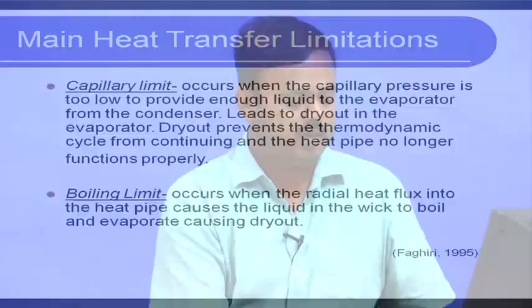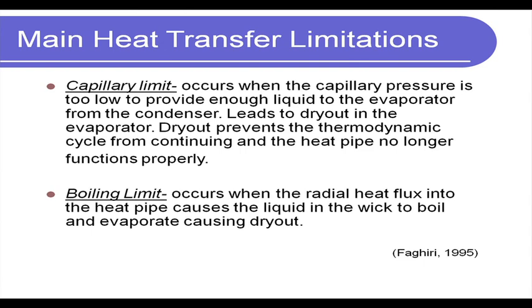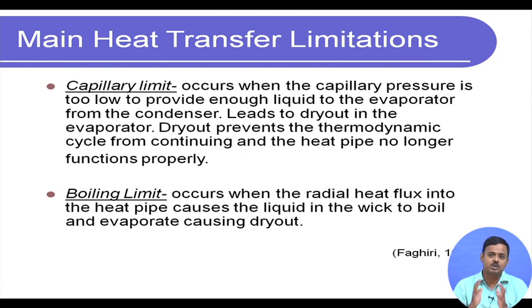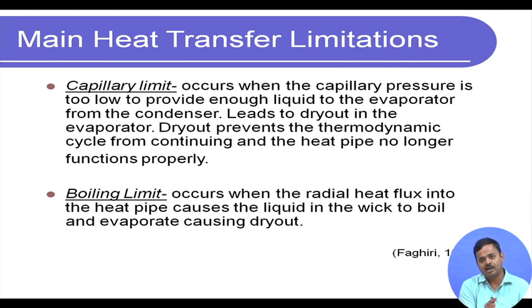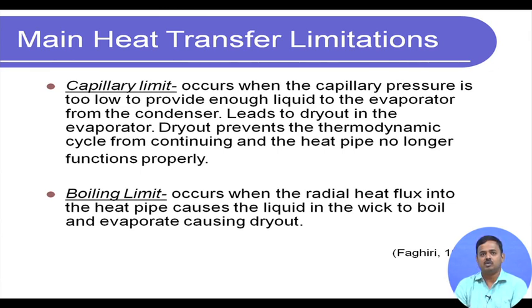Now let us go over the operating limits of a heat pipe. The first is the capillary limit: when the capillary pressure is too low to provide enough liquid from the condenser to the evaporator, leading to dry-out of the evaporator. If the capillary pumping head is insufficient and liquid cannot return to the evaporator while heat is being supplied, the liquid will vaporize and not come back, causing complete dry-out.